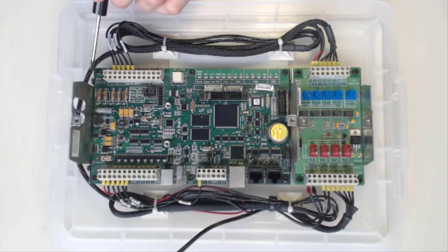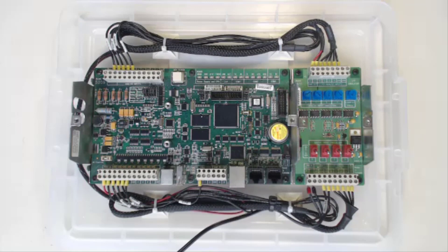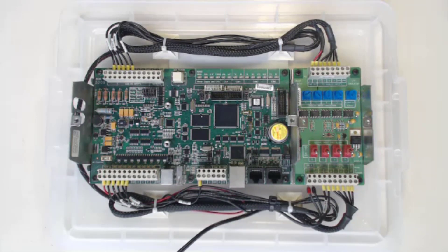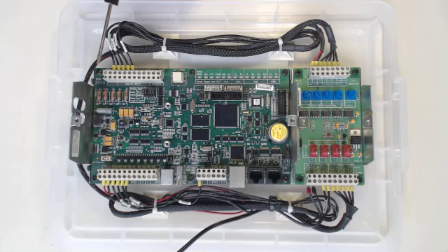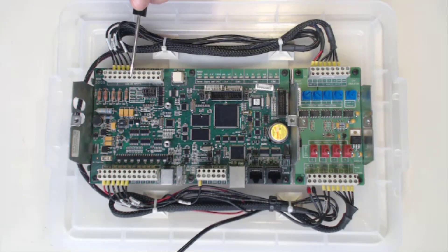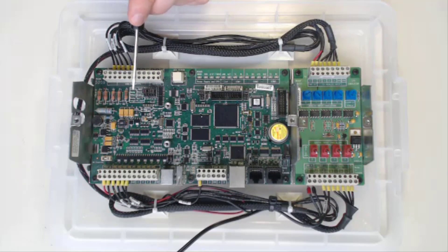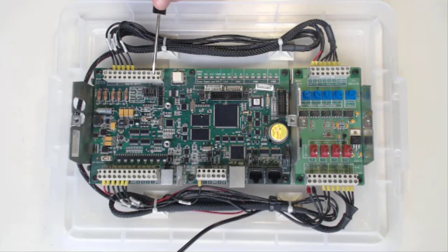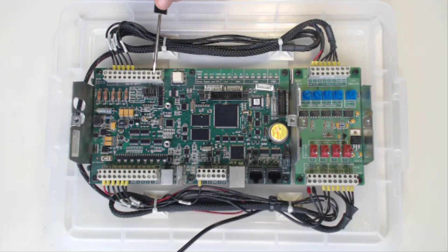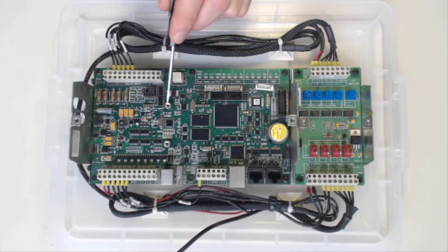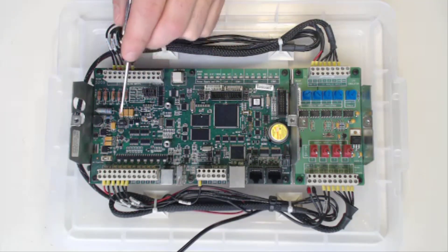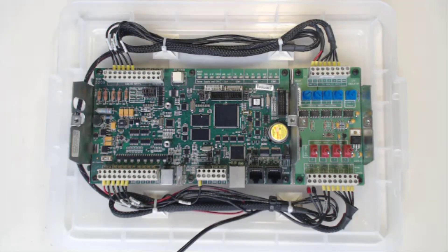When you pull the cover off, we're going to start at the top here where it says Model 5209. That's the board model of the SCADAPack 350 that we have. Beside that is the analog input. The analog inputs can be current or voltage; you just select the dip switches here. Next to that is the analog outputs. The analog outputs are always located here, but they may not be enabled unless you have the analog output daughter board mounted here, which we don't, so just ignore that for now.